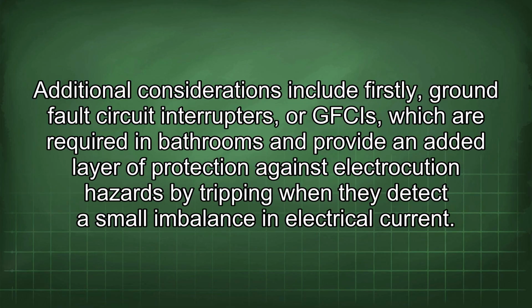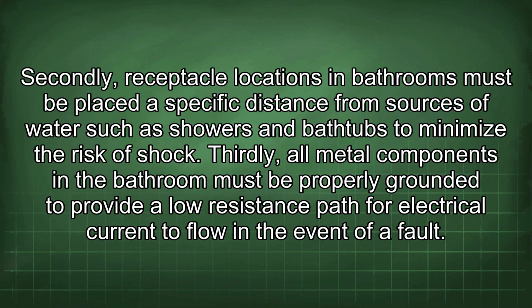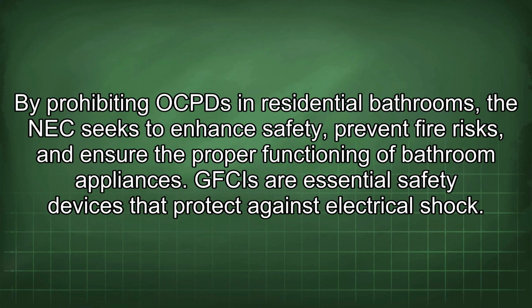Additional considerations include, firstly, ground fault circuit interrupters, or GFCIs, which are required in bathrooms and provide an added layer of protection against electrocution hazards by tripping when they detect a small imbalance in electrical current. Secondly, receptacle locations in bathrooms must be placed a specific distance from sources of water such as showers and bathtubs to minimize the risk of shock. Thirdly, all metal components in the bathroom must be properly grounded to provide a low resistance path for electrical current to flow in the event of a fault.